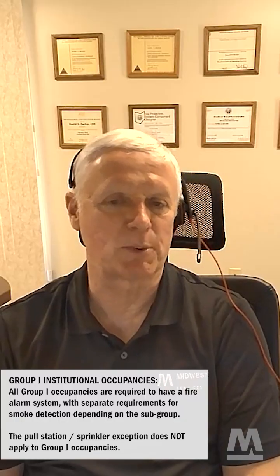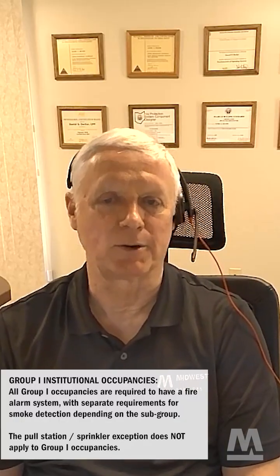Here's our exception that proves our rule. The pull station sprinkler exception does not apply to Group I occupancies. Instead, pull stations in Group I1 and I2 are not required at exits if they're located at a care provider control station, which we used to call nursing stations. Occupant notification is not required to be activated when private mode signaling is approved by the fire code official, and staff evacuation responsibilities are included in the fire safety evacuation plan. So this is pretty much exclusively healthcare.